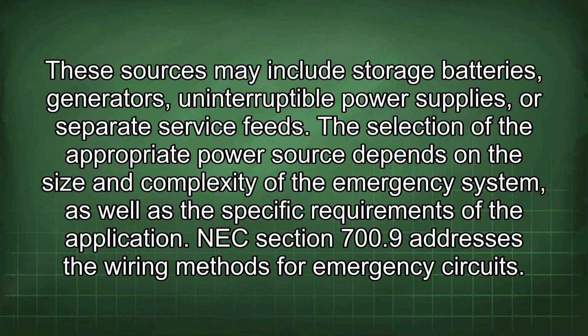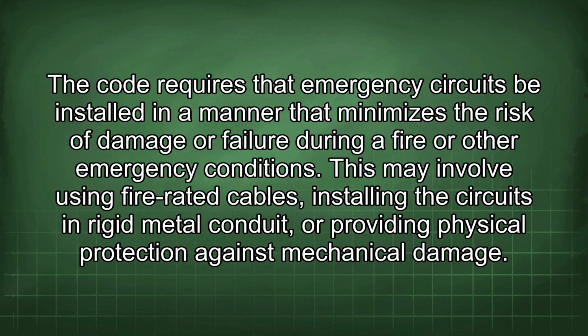The selection of the appropriate power source depends on the size and complexity of the emergency system, as well as the specific requirements of the application. NEC Section 700.9 addresses the wiring methods for emergency circuits. The code requires that emergency circuits be installed in a manner that minimizes the risk of damage or failure during a fire or other emergency conditions. This may involve using fire-rated cables, installing the circuits in rigid metal conduit, or providing physical protection against mechanical damage.